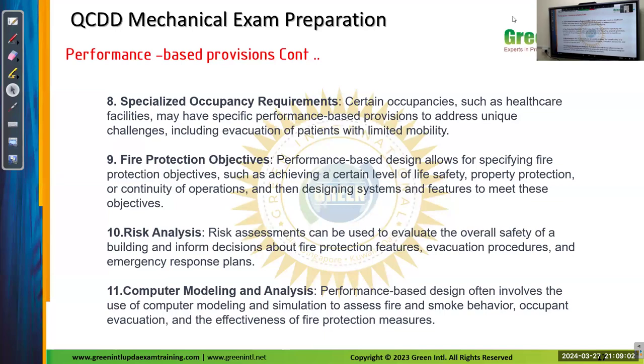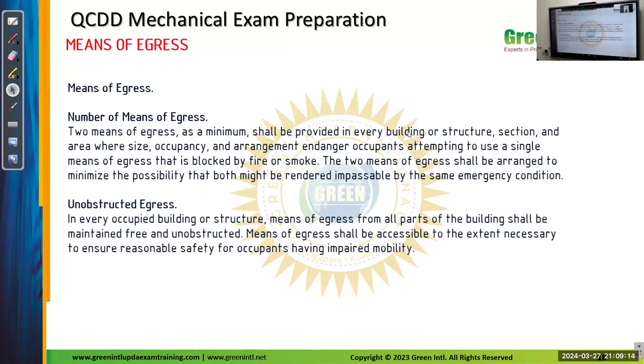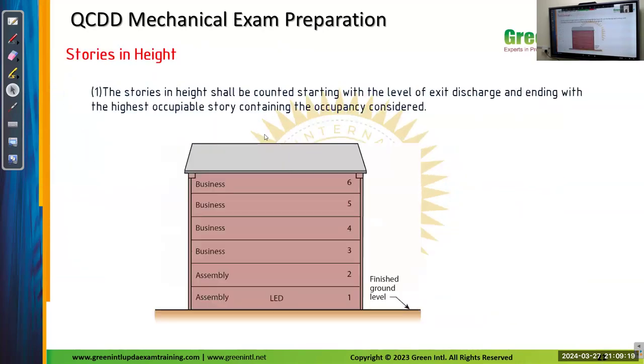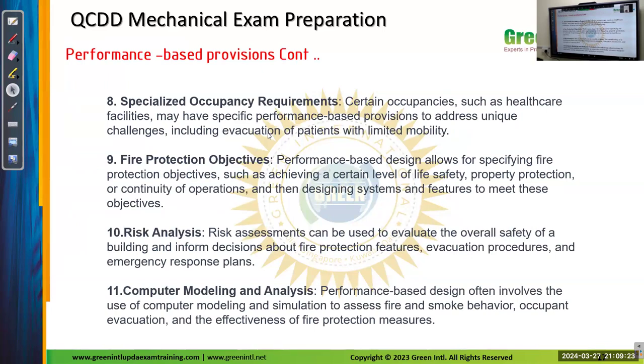In those systems, it is purely based on your requirements, whether it is fire protection objectives, risk analysis, or computer modeling. Each topic you will cover to meet your design requirements, and it's not mandatory that you follow the regulations. But the only disadvantage of this system is that you have to practically prove that this system is working or not. It takes time compared to the prescriptive-based system. This is the performance-based system.